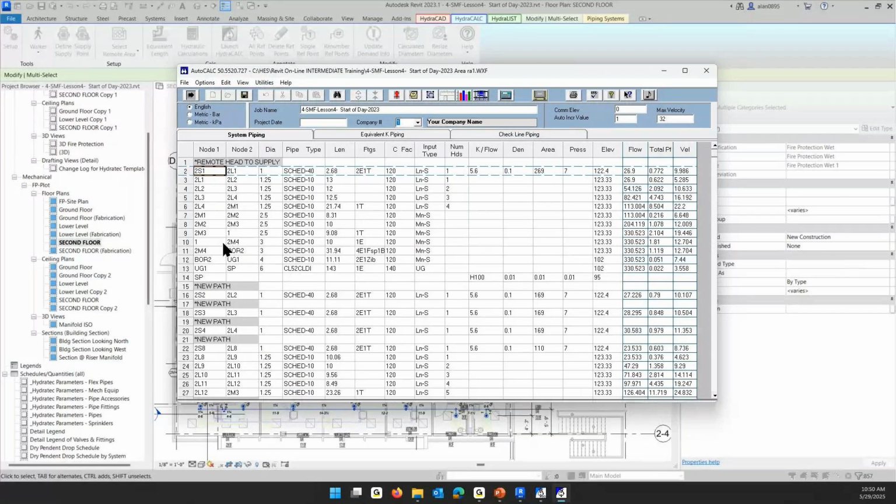So Josh, do you see what we've accomplished here? This is a lot, I think, a lot easier to read. Sprinkler 1 to branch line 1 to branch line 2 to branch line 3 to main 1, main 2, main 3. There's an extra reference point in there. And the extra reference point, I think, is coming from the fact that I've got 1.25 inches and 2.5. I forgot to apply the pipe sizes that we had figured out before.